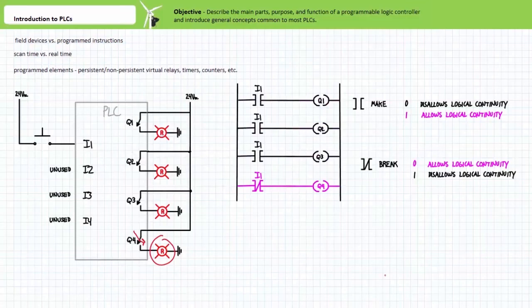In addition to the reprogrammable and field versus logical nature of PLCs, fundamental implementation differences exist between PLC programs and hardwired relay based ladder logic. Hardwired relay based ladder logic is implemented in real time, where real time is simultaneous or concurrent, whereas PLC programs are ordinarily implemented by the CPU using scan time.